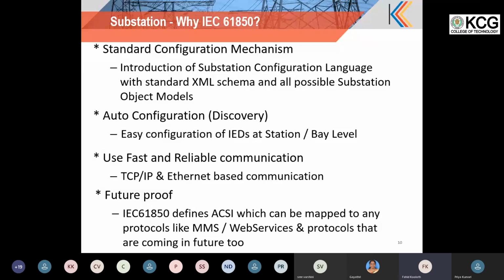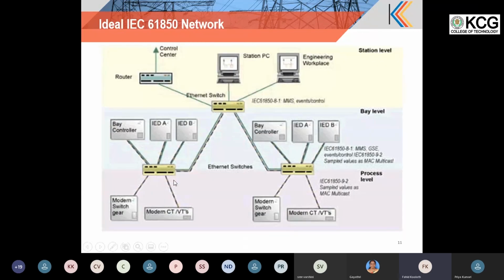So moving on to the ideal 61850 network. All the devices you can see, including the bottom line, you have process equipment, including CTs, VTs, and circuit breakers in the process level, and on the bay level, multiple IEDs and bay controllers are there.